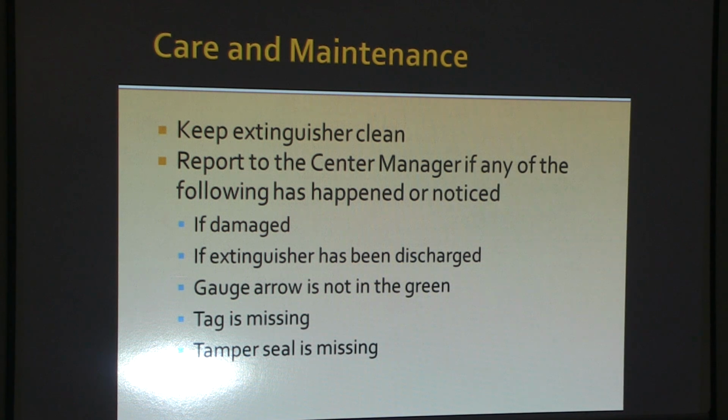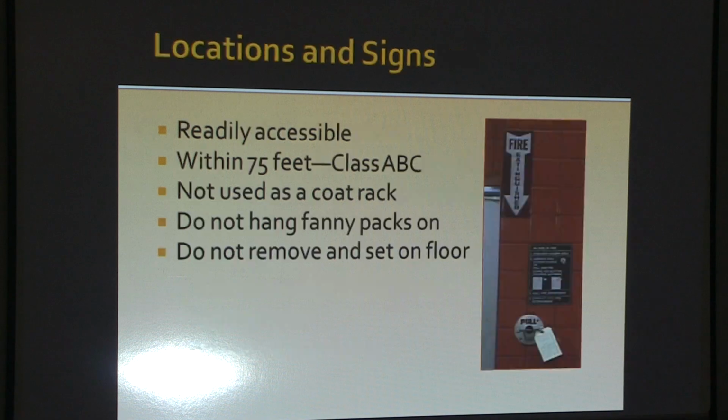Make sure they're clean. Report anything out of the ordinary to your center manager. If it's damaged, if it's been discharged, if the gauge, the arrow, is not in the green, or the tag is missing, or the seal has been tampered with, or it's missing.